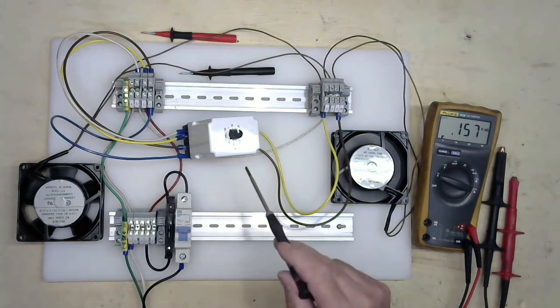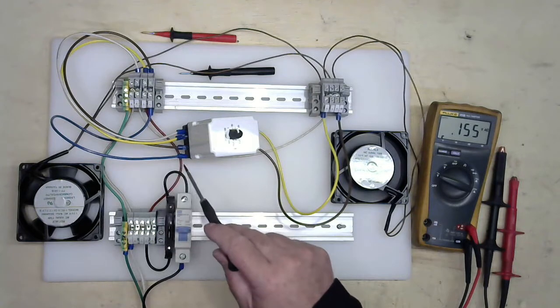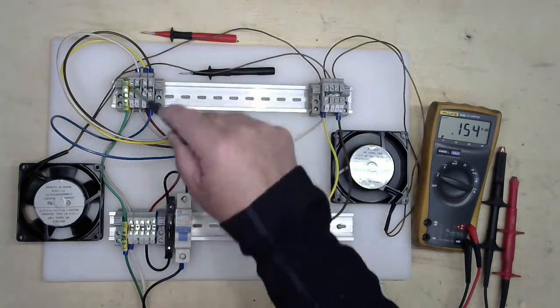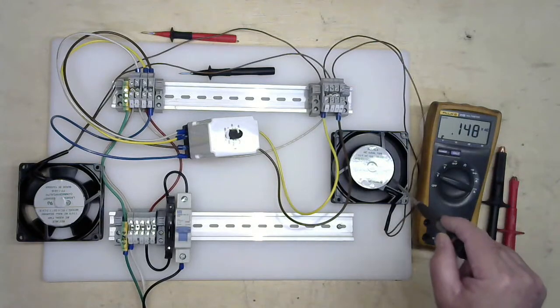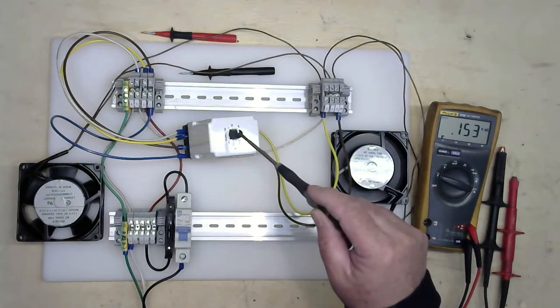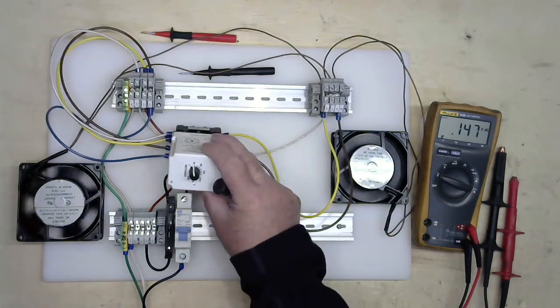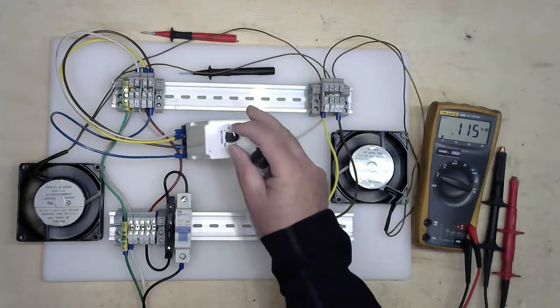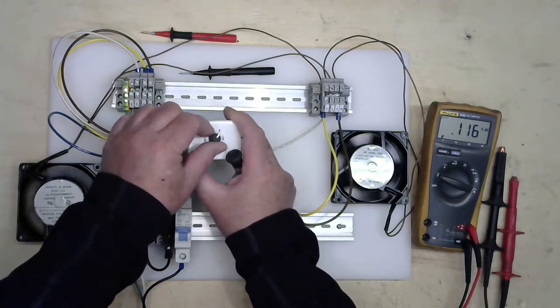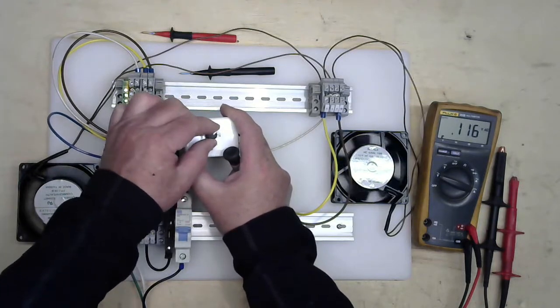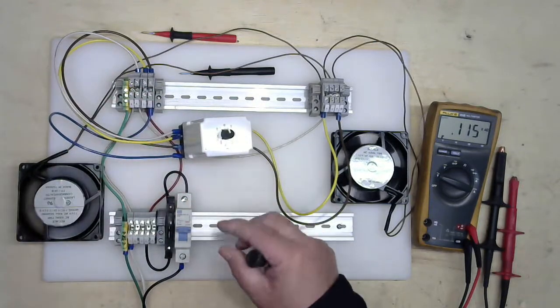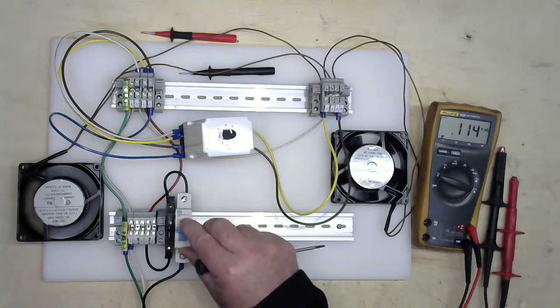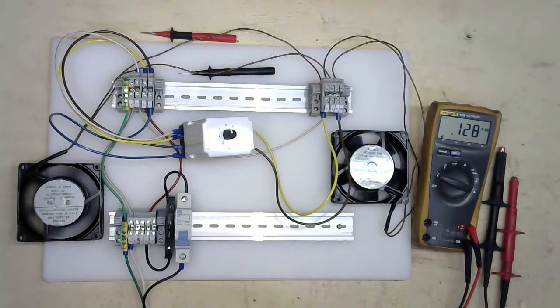As soon as I apply power, my normally closed terminals will apply power through my brown wire here to this fan, operating it. Once my timer times out, you can see the timing function is up front and has already finished timing. Once it's actually timing, as you can see, I can adjust this all day. It will not make any kind of difference once the coil has already timed its function. I'm going to go ahead and cycle the power off once again. Wait for my fan here to finish its rotation.